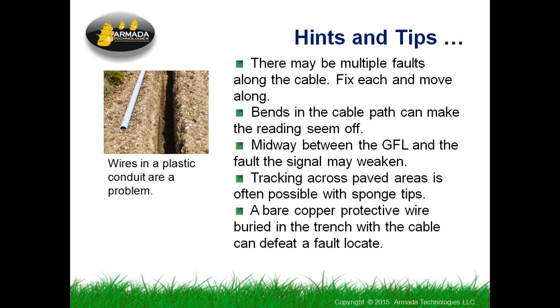Bends in the cable can cause some readings that don't seem to make very much sense. You just need to keep going along the path and see if you recover the normal kicks, because as the cable serpentines, as it disappears, as it crosses another obstacle, you may find some funny readings. But if you keep following the path, as you approach the problem, you will see the kicks and get the reversal you're looking for. So keep going is the watchword here.